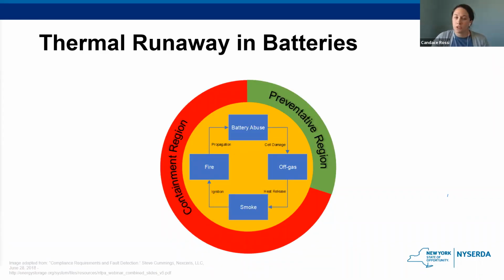One of the largest things that people are concerned about when it comes to energy storage events is thermal runaway. Thermal runaway is one of the primary risks related to lithium ion batteries. It is a reaction in which the lithium ion cell enters an uncontrollable self-heating state. Thermal runaway can result in off-gassing, high temperature, smoke, or fire, as you can see on the screen.